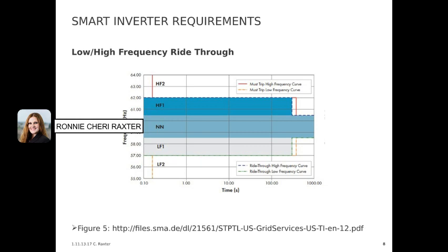This setting is low-high frequency ride-through, and similarly to the last two, this one has to be activated. This ride-through is referring to the ability of the DER to stay connected during high or low frequency events for a predetermined amount of time. The Rule 21 high-frequency tripping time, in comparison to what it used to be, has been shortened. However, the mid-range tripping time values have been extended.